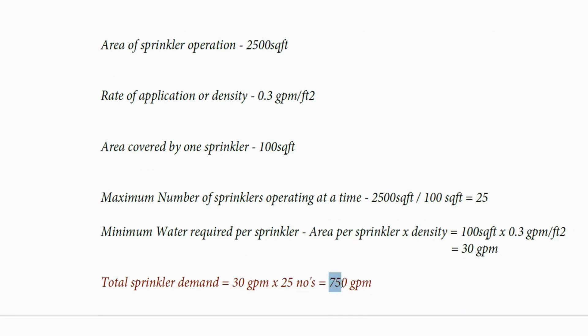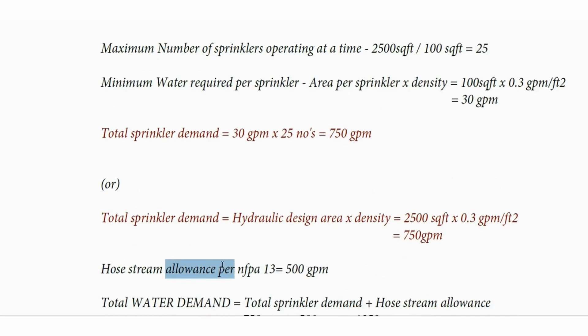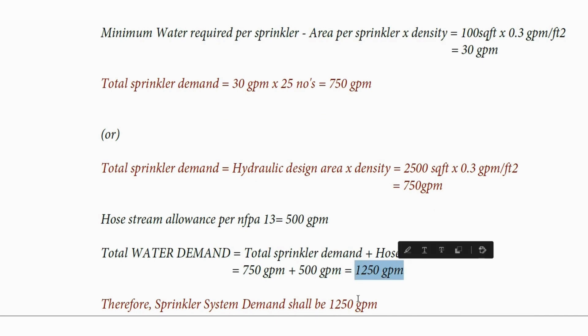Multiplying 30 GPM by the total number of 25 sprinklers, we get a sprinkler demand of approximately 750 gallons per minute. Adding the hose stream allowance per NFPA 13 for extra hazard, which is 500 GPM, gives 750 plus 500 equals 1250 GPM total water demand. In the same way, we can calculate the sprinkler system demand for extra hazard group 2 occupancy.